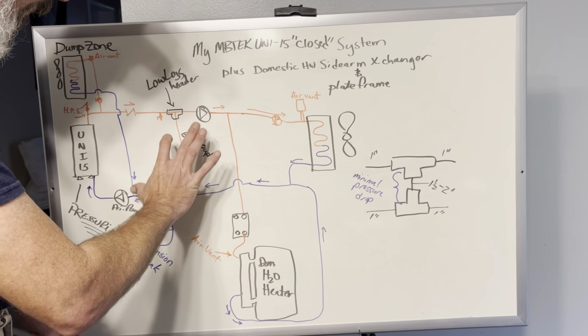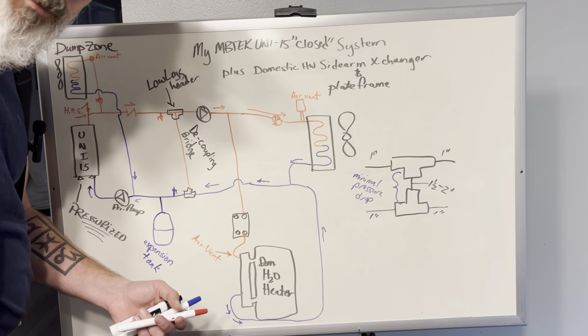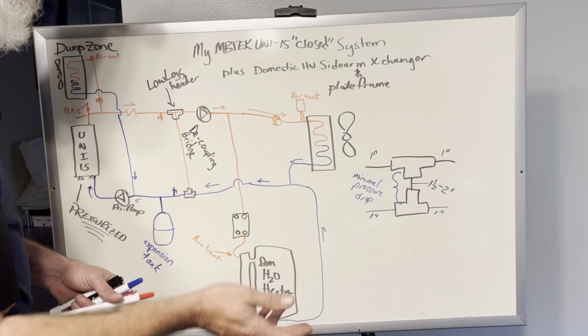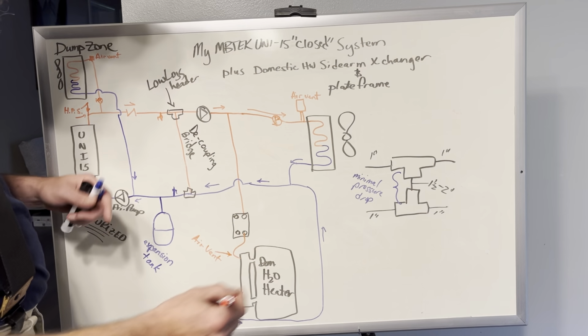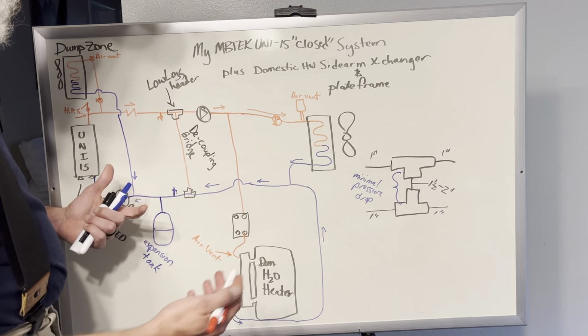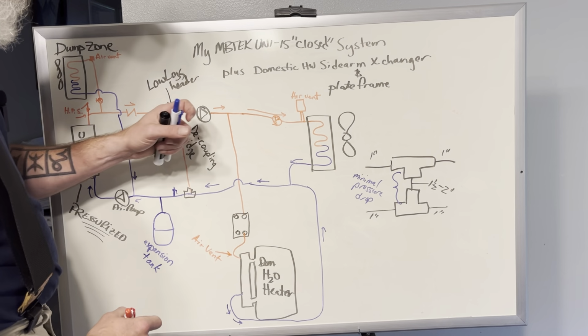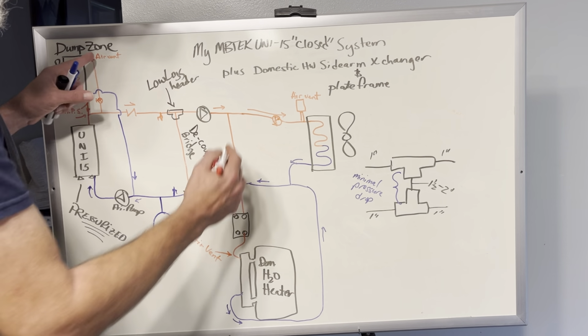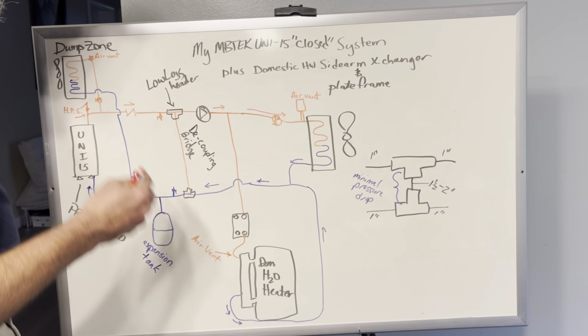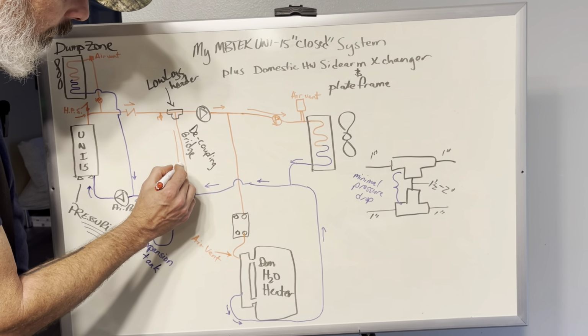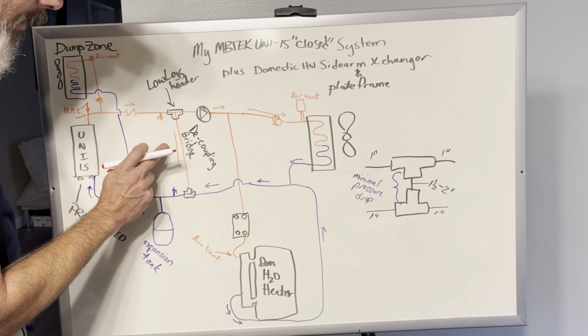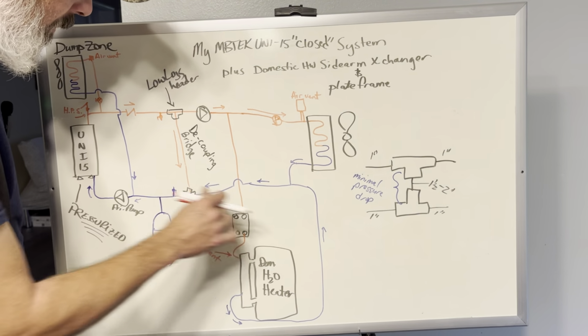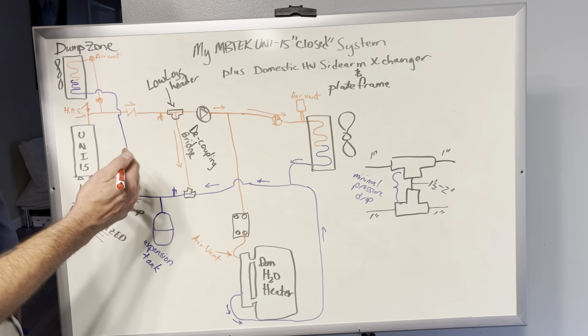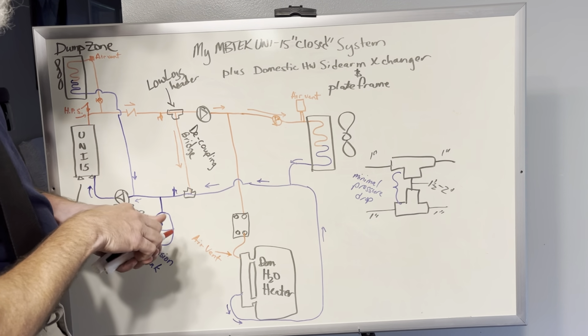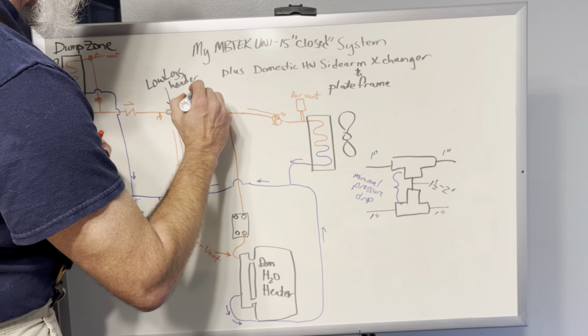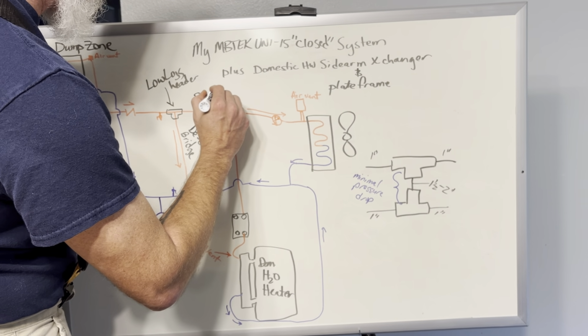Now, I have constant speed pumps. If you had variable speed pumps, say with zoned radiant in-floor heat, you may have variable speed and this changes. In my situation, I've got fixed speed, and circuits just open or close. So basically I'm always moving water some amount right there, and the amount depends on what's happening on this side. So here's my secondary pump. This is my house side.